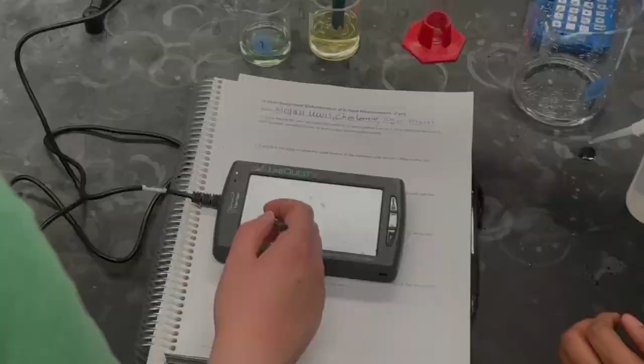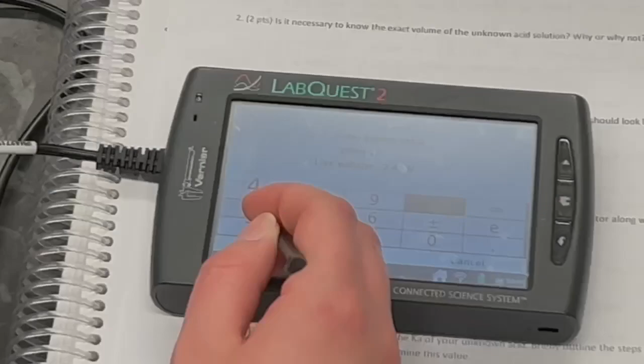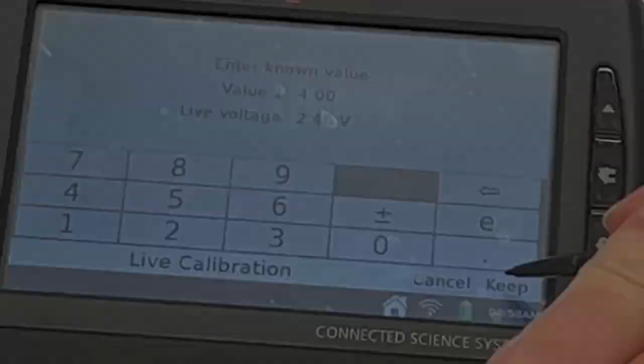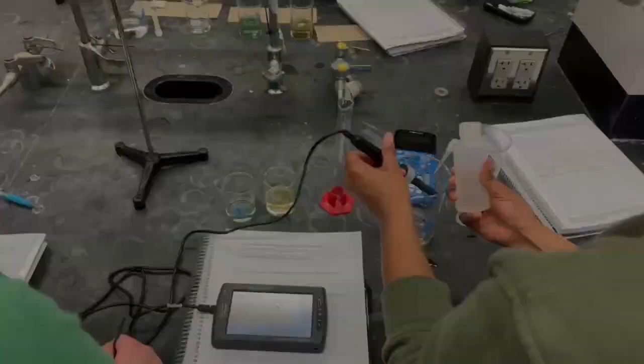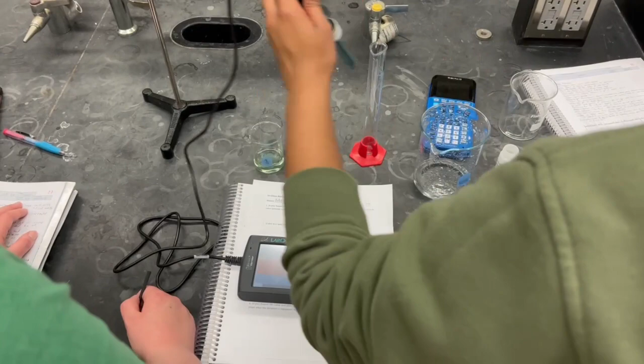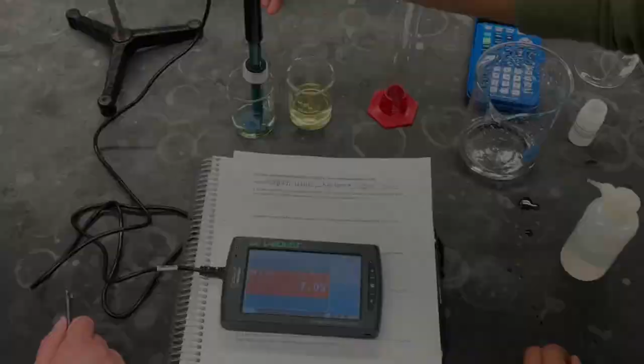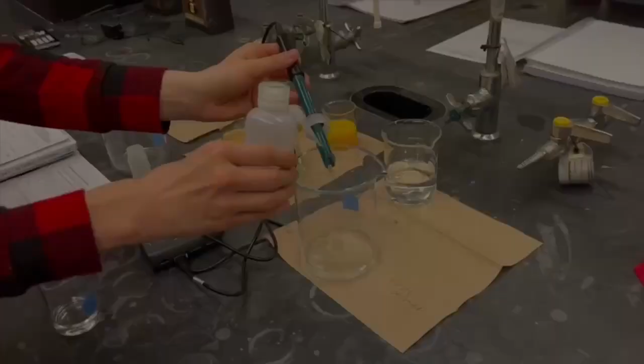Next, rinse the probe again and put it into the pH 4 buffer solution, and then input that value into the meter. After that, you would rinse the probe again and place it back into the pH 7 buffer solution to test that it is properly calibrated. Finally, you would then rinse the probe with the distilled water and place it back into its container.